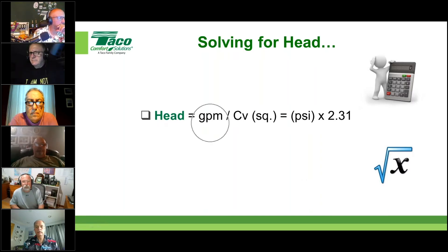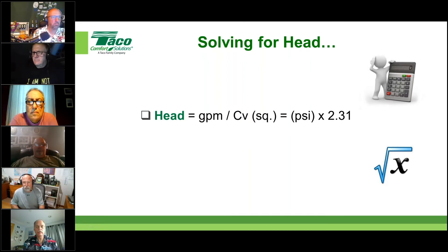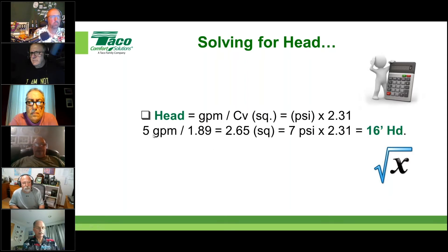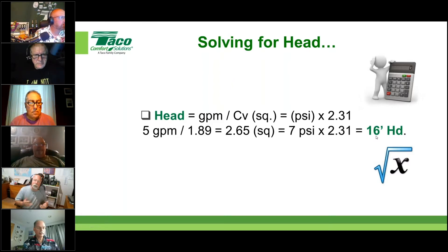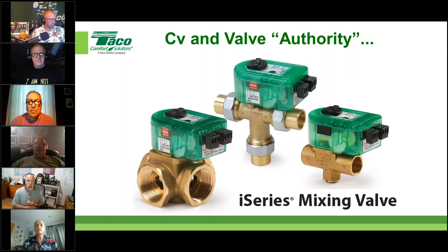Here's the calculation simplified. To solve for head, take GPM divided by the Cv of the valve, square that result to get PSI, then multiply by 2.31 to convert PSI to feet of head. For example: five GPM through a valve with a Cv of 1.89 gives 2.65; squared is seven PSI; times 2.31 equals 16 feet of head. That's how we use Cv to estimate pressure drop.